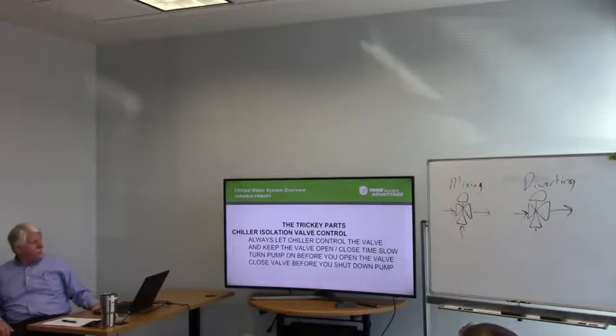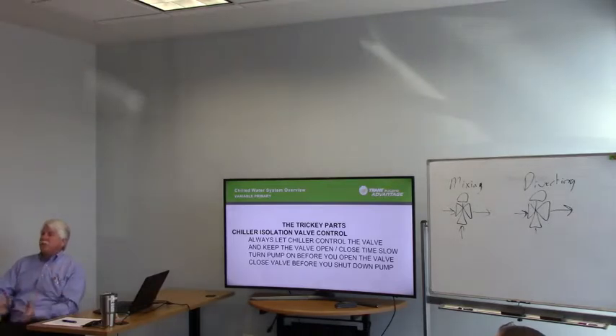Okay. Chiller isolation valve: always let the chiller control the valve, and keep the valve open and close time slow. Turn on the pump before you open the valve. Okay, if you turn on the pump before you open the valve, think about it, on our valve control.